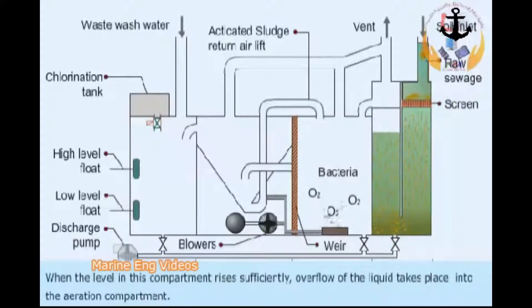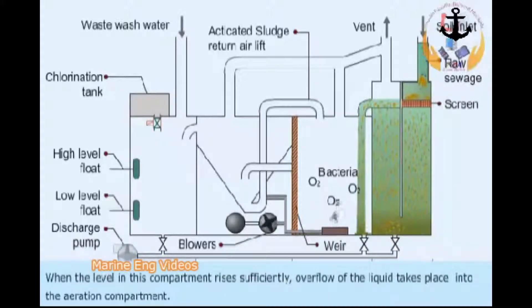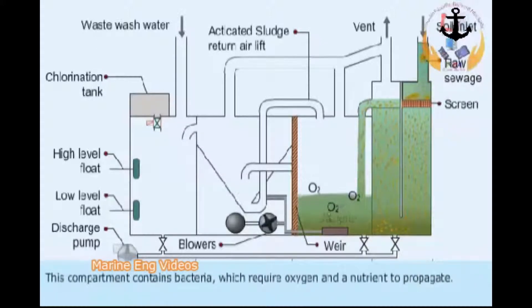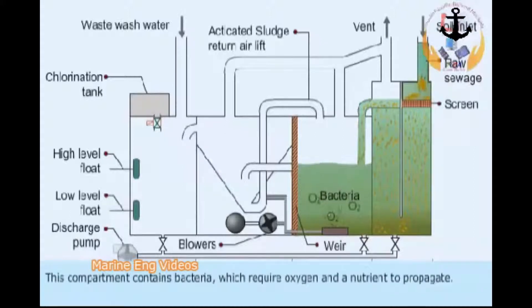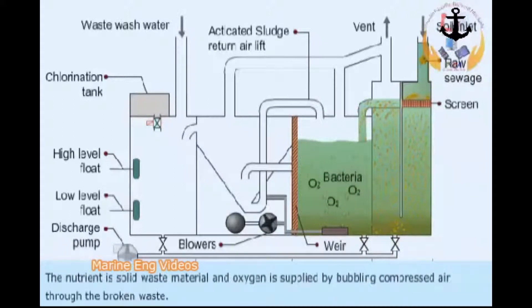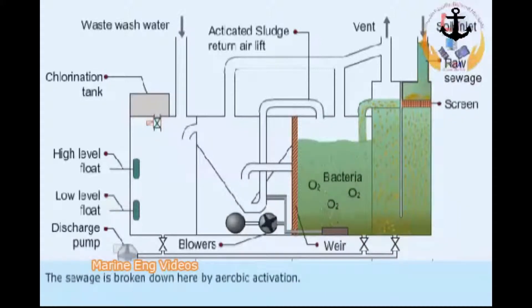When the level in this compartment rises sufficiently, overflow of the liquid takes place into the aeration compartment. This compartment contains bacteria which require oxygen and a nutrient to propagate. The nutrient is solid waste material, and oxygen is supplied by bubbling compressed air through the broken waste. The sewage is broken down here by aerobic activation.